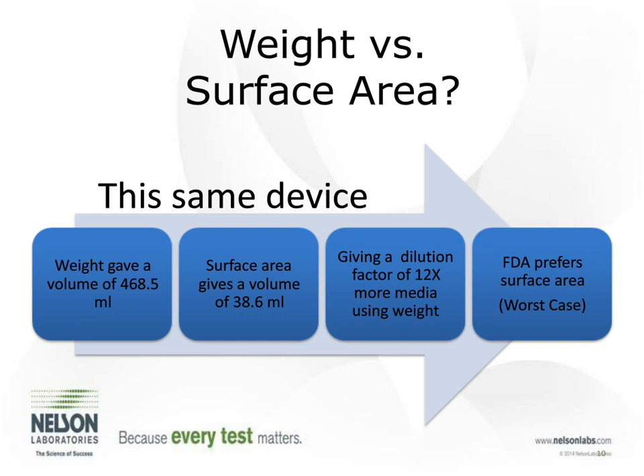So if you perform weight, the FDA is probably going to ask you why you chose weight. And we have to be really thoughtful on our choices when we're doing a sample preparation, on what choice we choose, or else the FDA or any regulatory agency could have a big impact.